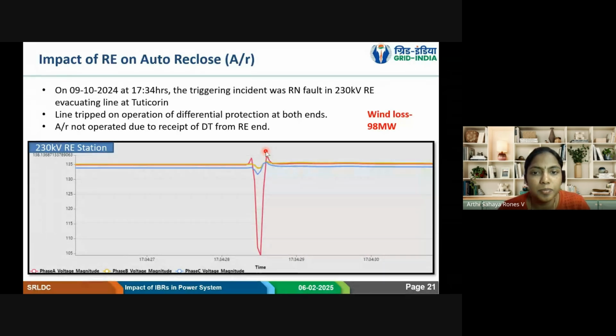And ideally, we expect it to happen properly. So one such case is presented here. There was just one RN transient fault in the system, but the evacuating line didn't attempt auto reclose. It tripped. It had sent a direct trip to the grid end, and both the ends got tripped. So in this case, there was a differential protection.